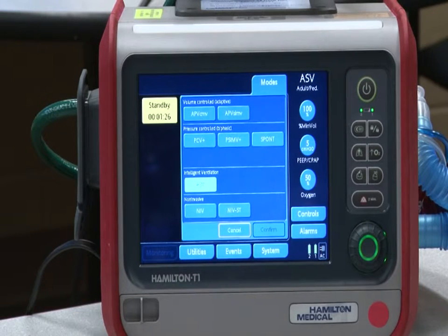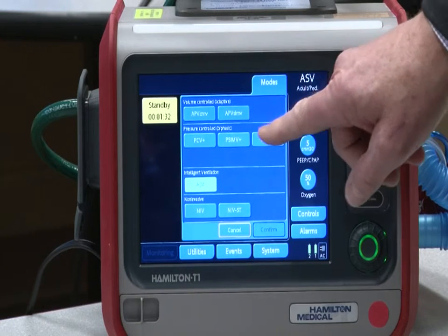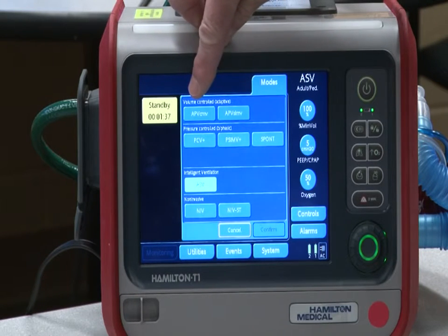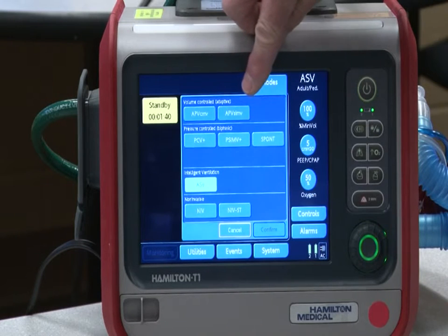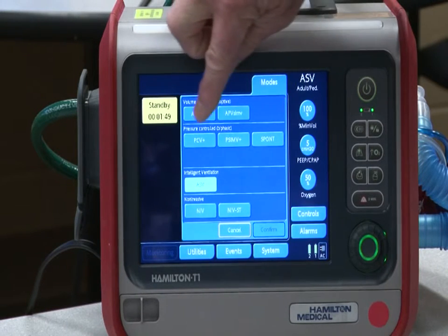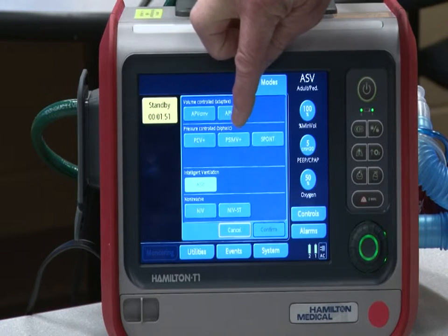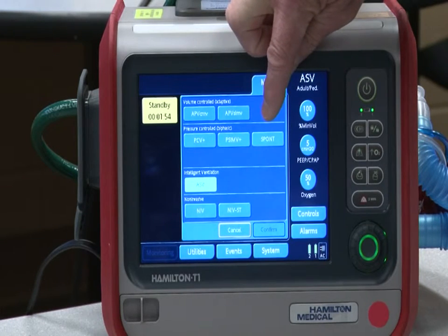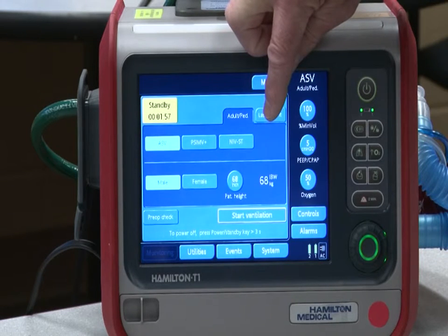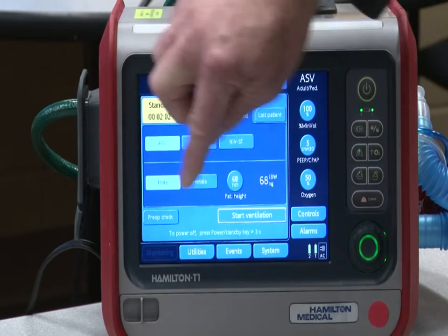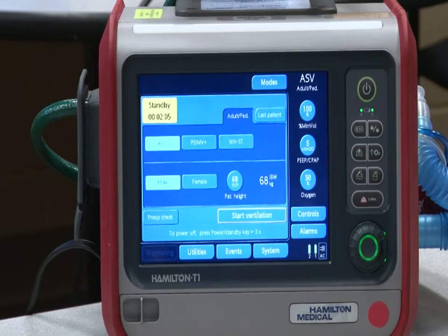So if you press the modes key, you'll see that ASV is illuminated, which means that's the active mode. And in that second grouping here, PSIMV, that's that same mode. These top two are the volume targeted pressure control without the adaptive stuff that's included in ASV. So that's just straight volume targeted pressure control. The next grouping are all the pressure control modes. So that would be the assist control, the SIMV version, and the spontaneous. So that would be, you wanted to put the patient on BiPAP, but they were already intubated, but you didn't really want to apply any of the other stuff of positive pressure ventilation. And then the bottom two are the non-invasive modes. And we'll talk more about those as we go along as well.